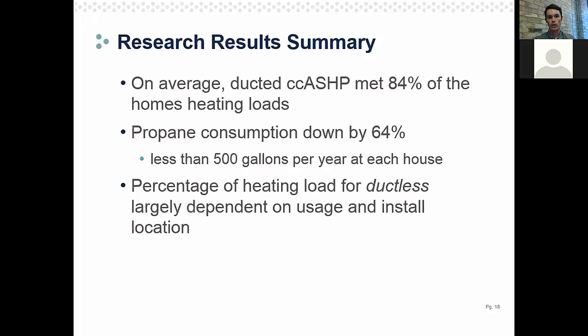So a summary of what that meant is with that ducted dual fuel system, the cold climate heat pump is meeting the home's heating load 84% of the time. So it's meeting that home's heating load for the majority of the winter. That other 16% is when that propane furnace is operating. And what that does is it reduces a homeowner's propane consumption by 64%. For most homes, what that's going to mean is less than 500 gallons of propane used per year. And the huge benefit of that is 500 gallons is typically the size of your propane tank.